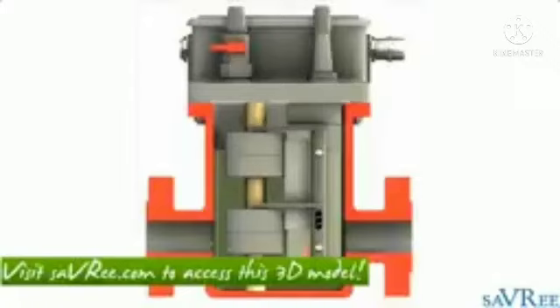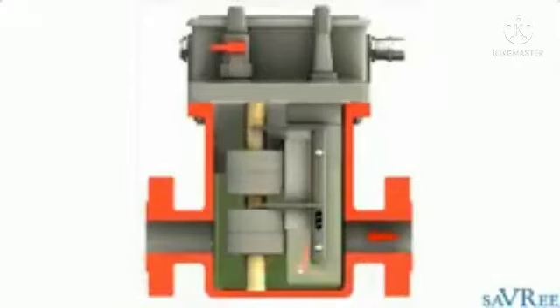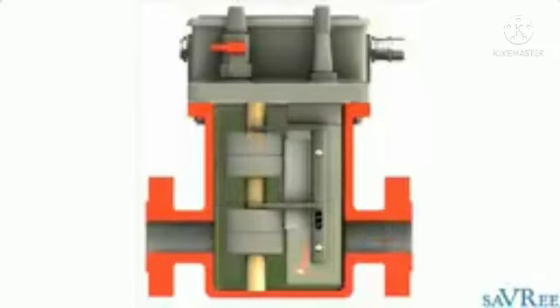So, if we have a small electrical fault within the transformer, we're going to heat up the insulating liquid, and this is then going to generate small bubbles of gas. The small bubbles of gas are going to slowly accumulate within the Buchholz relay. They're going to push a float downwards, and then we are going to set off an alarm which tells the engineers that there is a small electrical fault within the transformer.